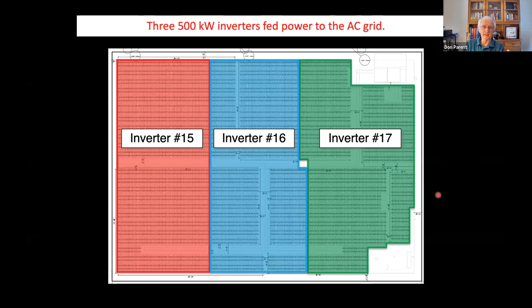So this is a result of the analysis of that Excel data. And what you see here is in July of 2012, a 3502 ground fault error that occurred on that inverter. And that is inverter 16. Now that's the year before the fire. A 3502 fault can only be cleared by somebody going into the electrical cabinet of the inverter, unlocking the door manually, flipping the breaker, because that error is trapped or identified by a 5-amp breaker, resetting that breaker, closing the door, and restarting the inverter. That happened because that error was cleared and the system was put back into operation.